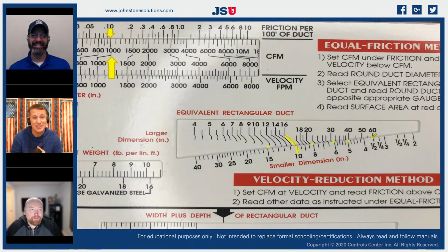So this is the issue that I got into with this other contractor. He was wanting to use wall stack to run 6-inch registers. Wall stack is 3.5 inches. So I can run a bunch of airflow in a 3.5-inch cavity between two studs. But if I needed to run 1,000 CFM between those studs, I need 60 inches between those studs, 5 feet between those studs to be able to move 1,000 CFM unrestricted.